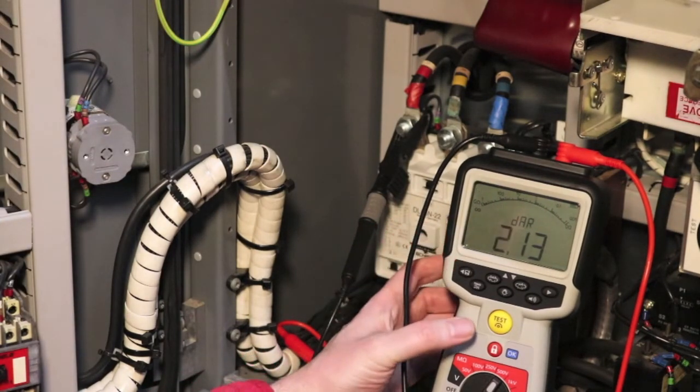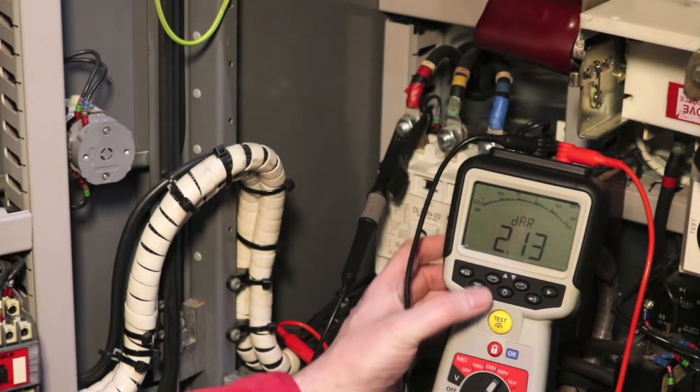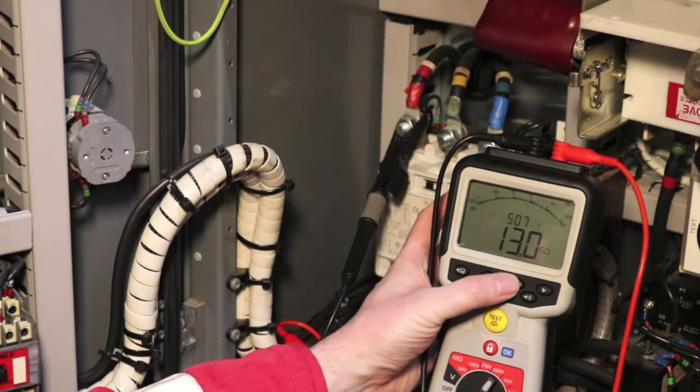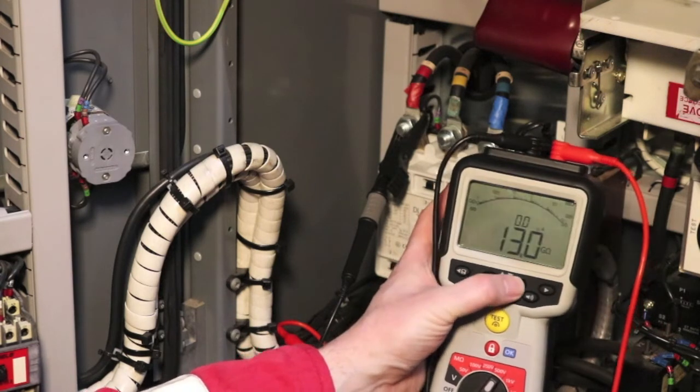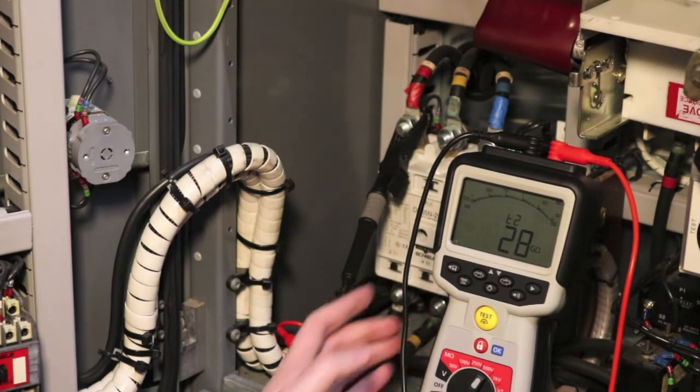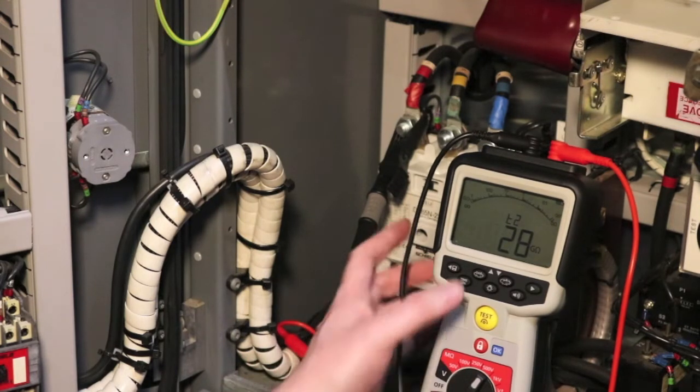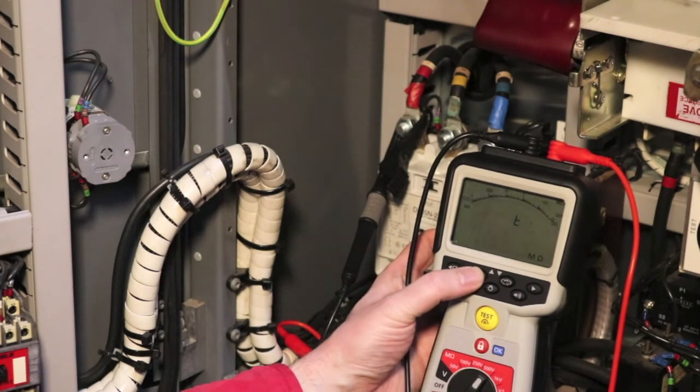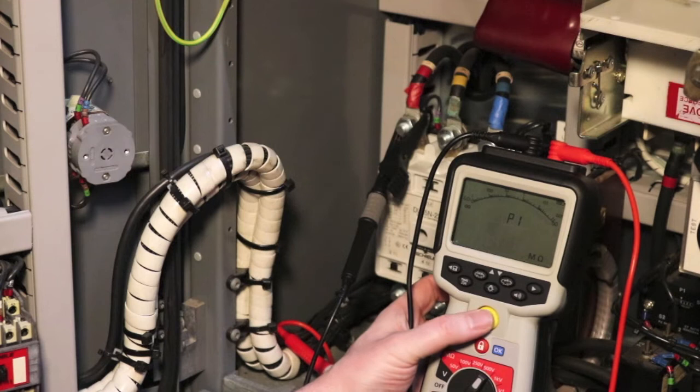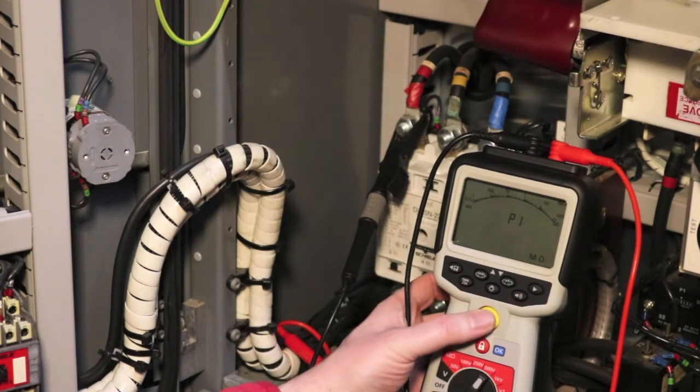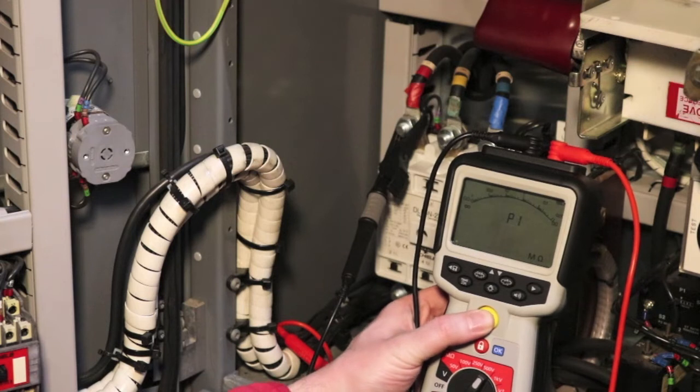So we'll save that reading there and then using the function button I can work my way through all the readings that it took at the 30 second and the 60 second and record the values and the voltage that the test was completed at. So once we've done that, use the function button and we'll set up for a polarisation index test and then we can start that one. Again it will be at 500 volts.